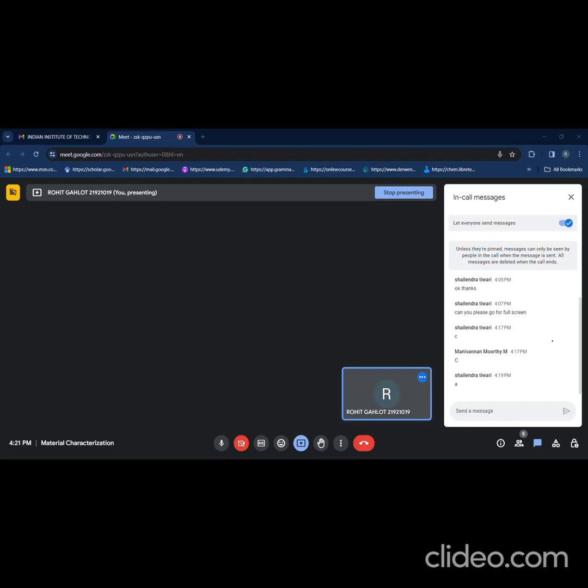So this was the last lecture. It was taught in the effect of condenser lens strength. Increasing your condenser lens strength increases the demagnification of each lens and reduces the probe size. Further, the final probe size can only be reduced at the expense of reducing the probe current, and a conscious choice is needed between minimizing probe size or maximizing probe current. Okay. So the correct answer will be decreases. Now if we move to the ninth one, if we increase the condenser current, what will happen to the final probe current? This will also reduce.